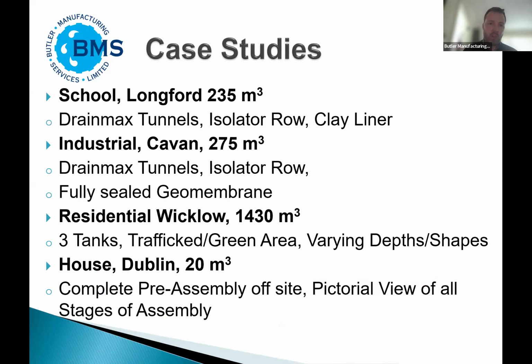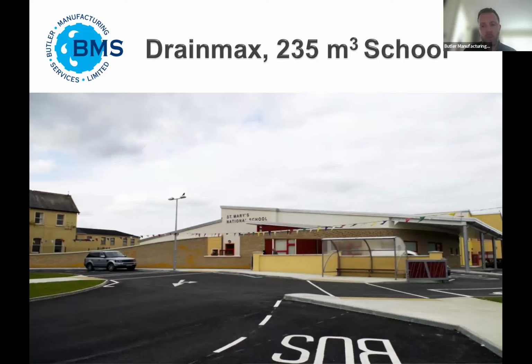Before I start, people often ask when do you put in the tunnel systems and when do you put in the crate type systems. Tunnel type systems are ideal especially when there's not very high loading and we can achieve enough cover, and also because you can include a lot of stone with it and there's a lot of space available. They will generally be our recommended solution if you have enough space and can provide adequate cover. They are very strong and provide for 1 ton, 10 ton axle loading, but they need a meter of cover over them, whereas crates need less cover, maybe up to about 600 millimeters, and they can go in tighter spaces and achieve more attenuation volume in a tighter space, although they are more challenging to put in.